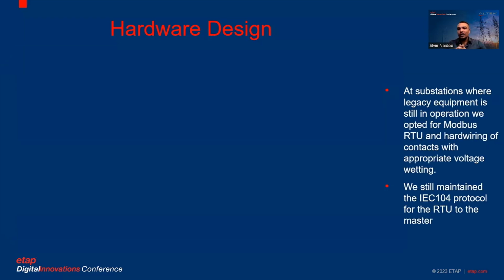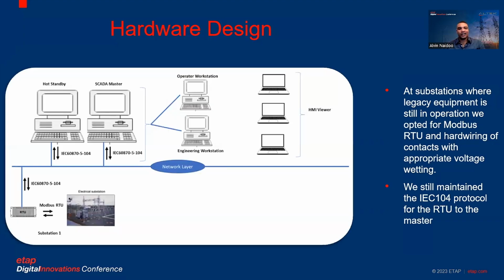So for the legacy equipment, we handle things a bit differently, because we did have Modbus RTU available at certain points. So RS-485 was utilized. And for certain pieces of equipment where there was zero communication available, we utilized hard wiring on the contacts with the appropriate voltage rating to the RTU. Now, at the RTU to the master station, we still maintained the IEC 104 protocol, which led us to an architecture looking like this.